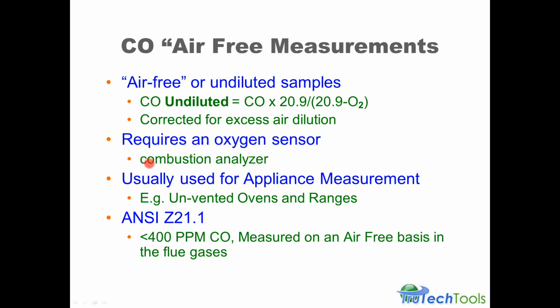using a combustion analyzer. There's still some CO-only meters out there, although those are less and less prevalent as the prices on combustion analyzers are coming down. We're seeing more and more people using combustion analyzers, which is a good thing. And this air-free measurement is usually used for appliance measurement for unvented ovens and ranges, because there the oxygen level is so high when it's unvented and you're taking a sample that you really need that in order to be able to interpret an undiluted reading.